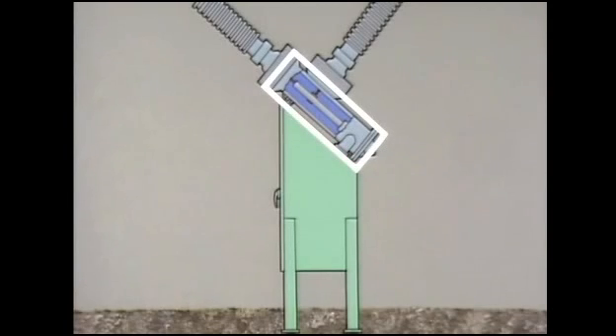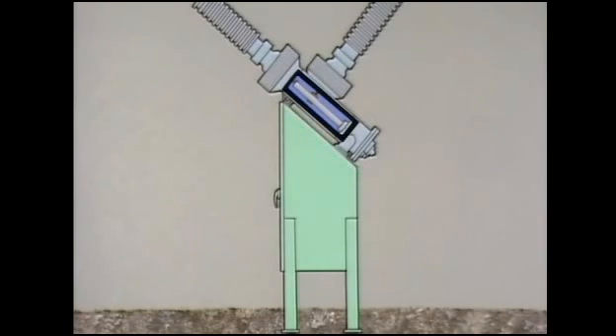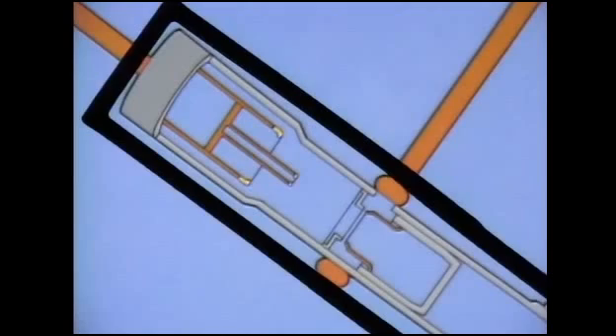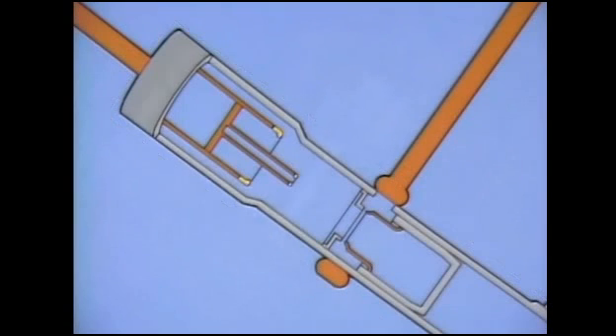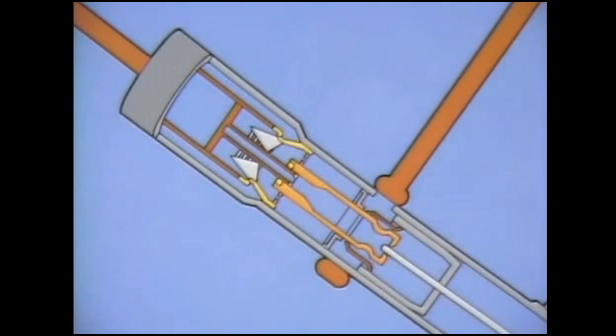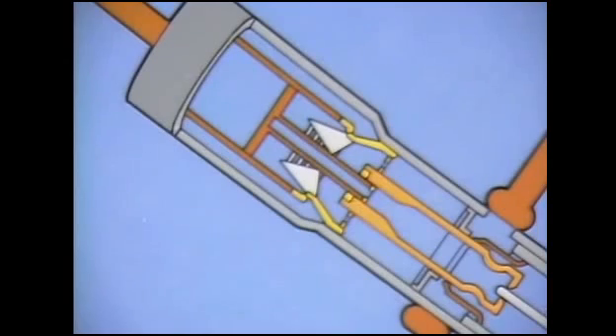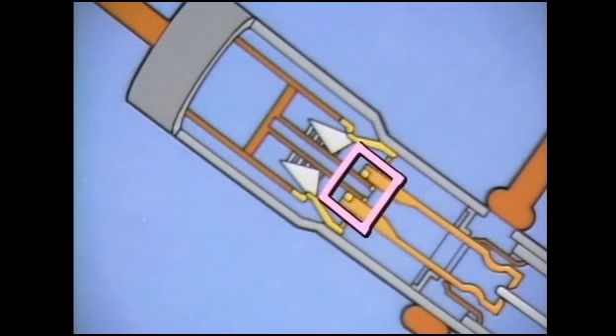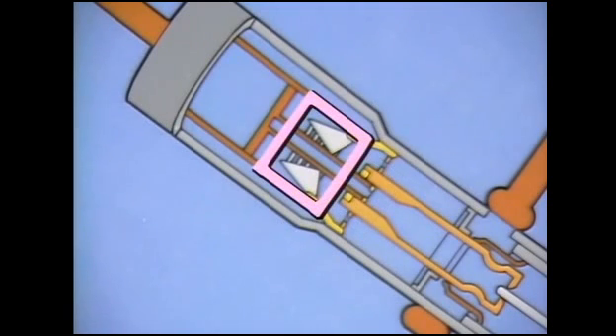The interrupter is enclosed in a pipe-like tank. The interrupter is an insulating tube which houses the interrupting mechanisms and insulates them from the outer tank. The main arc extinguishing features of the interrupter include a stationary contact assembly, a moving contact assembly, and a chamber where gas is compressed during the operation of the breaker. Each of the contact assemblies includes main contact fingers and arcing contact fingers. The moving contact assembly also includes a non-conducting nozzle.